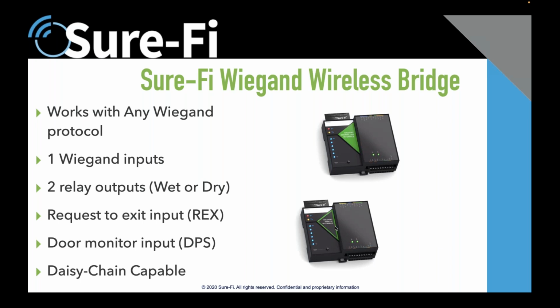One of those relays coming back would trigger the gate, but it has space—a lot of times the other relays are used for a request to exit or a door position sensor, something like that. This controller interface just goes near the access control panel, wiring in the Wiegand wires and all the relay wires, so the panel doesn't even realize it's not hardwired. The Wiegand controller interface essentially mocks all of that on that side, and the remote interface out at the gate acts as if it were an access control panel, putting the Wiegand device on those inputs and hooking up the relays.